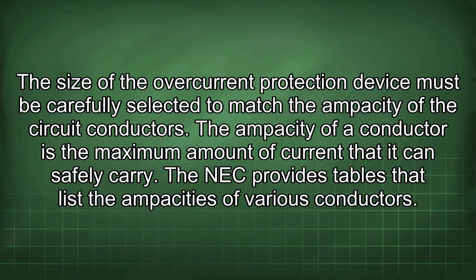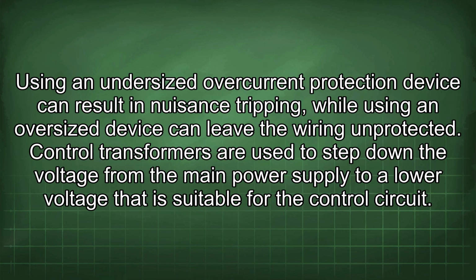The size of the overcurrent protection device must be carefully selected to match the ampacity of the circuit conductors. The ampacity of a conductor is the maximum amount of current that it can safely carry. The NEC provides tables that list the ampacities of various conductors. Using an undersized overcurrent protection device can result in nuisance tripping, while using an oversized device can leave the wiring unprotected.